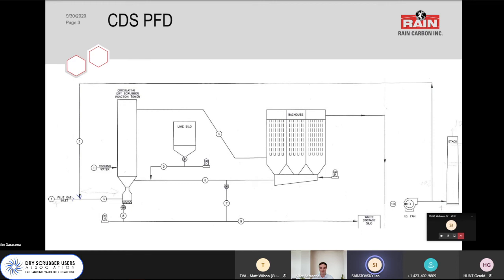Is water injection definitely needed for improving reaction efficiency in the process? Yes. That's incredibly important. At our DSI system, we have temperatures around the economizer outlet, which is 350 to 400. Our CDS systems are running at low to mid 200s, and they're vastly, 2 to 3 times, more efficient than our DSI system. It's incredibly important. Additionally, with CDS in general, the bags in our baghouse are not designed for the high temperatures at the economizer outlet. So from a design perspective, it's necessary as well.